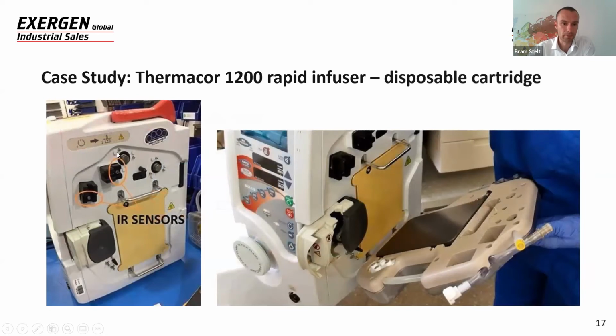So in the system are two sensors. You see them here. These are our IR sensors. One measures the inlet temperature of the blood, the temperature of the blood that's coming in. The other measures the temperature of the blood that's going to the patient. And depending on what the temperature difference is and what the required blood flow is, the system calculates how much power needs to be generated, or how much heating power needs to be put into the system, to warm up the blood sufficiently. And especially the second sensor that measures the outlet needs to make sure that the blood is 37 degrees. Also, what you see here is that the sensors are integrated into the body of the system.